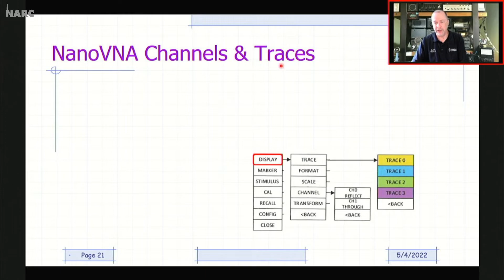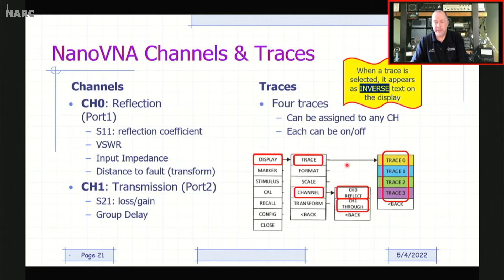And then for each of those channels, you can decide what traces you want to be used for those channels. If you only want to measure SWR, you could turn off all the traces except one of them, tell that one trace to look at channel 0, and then everything else is ignored and not put on the screen. Okay. So you pick a trace, and once you select the trace it kind of shows up in inverse text, then tell it which channel you want that trace to be applied to. Okay. So you set that up first, and then you go, okay, what trace formats do I want to have?